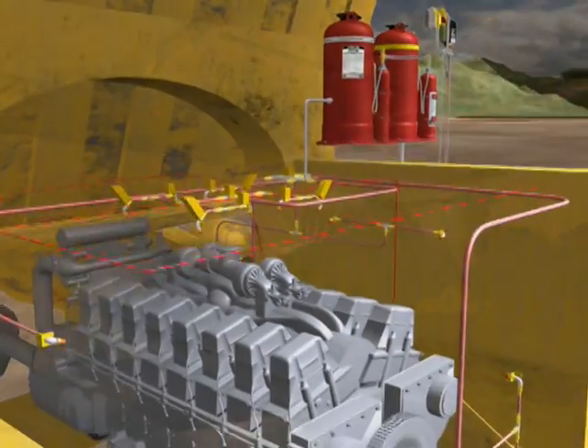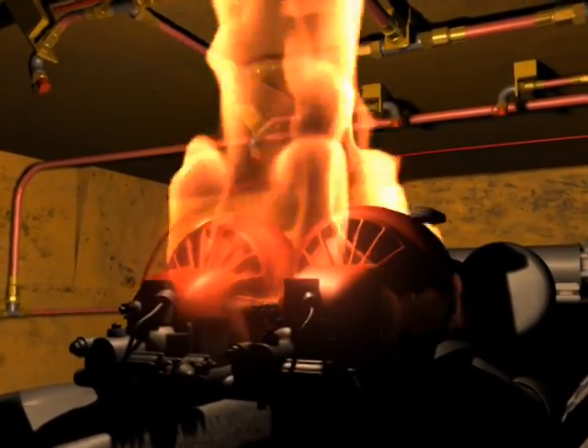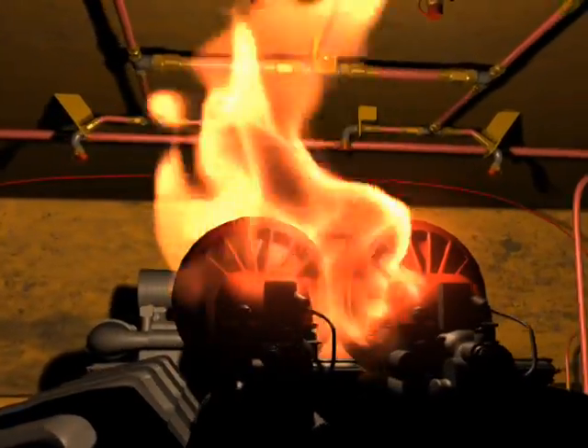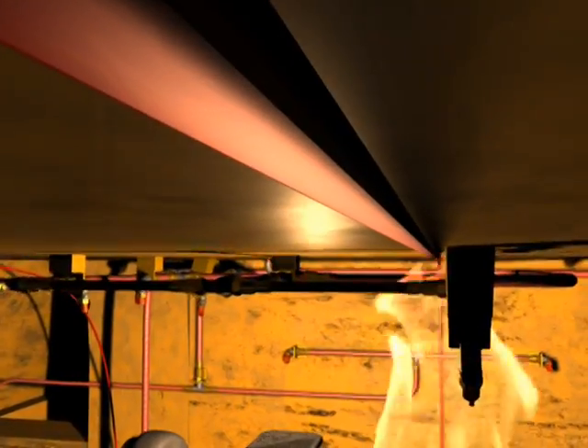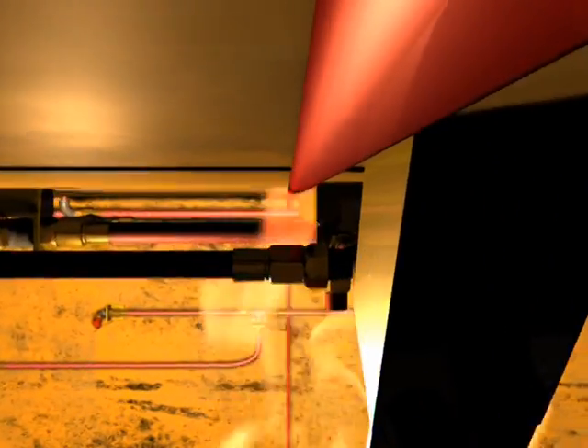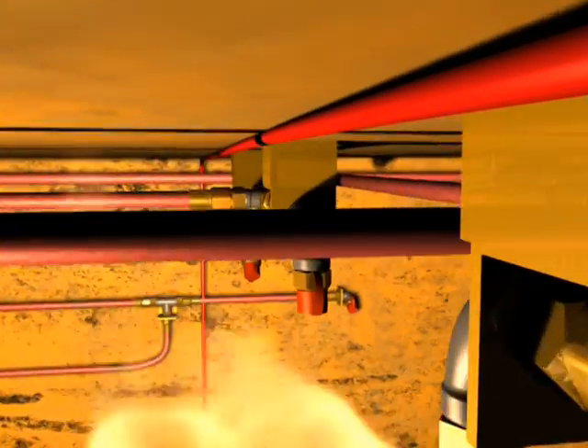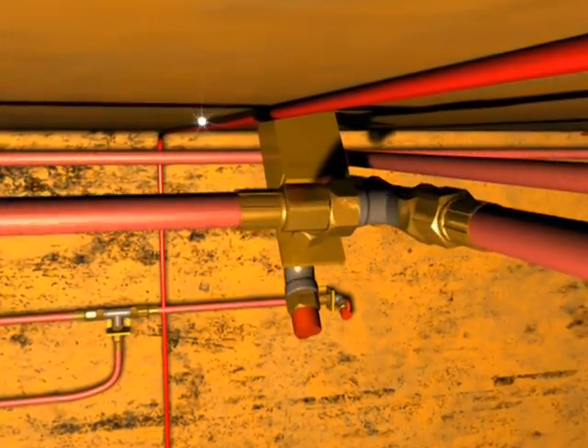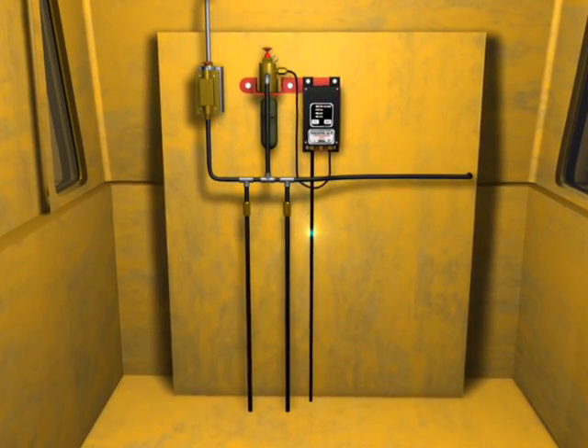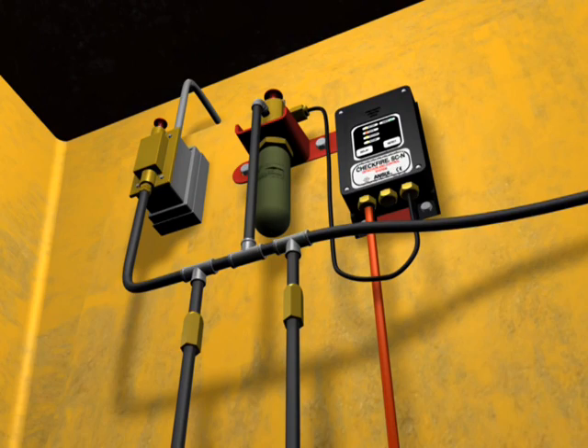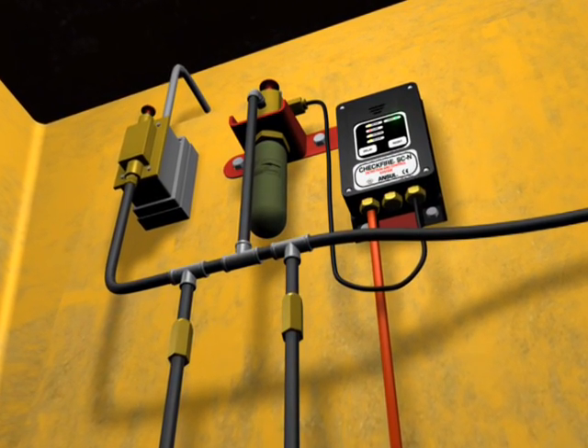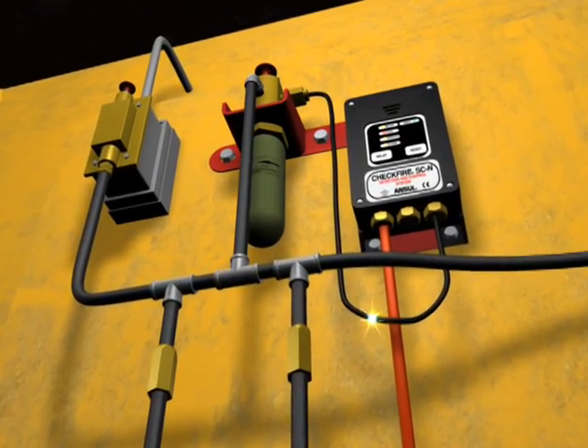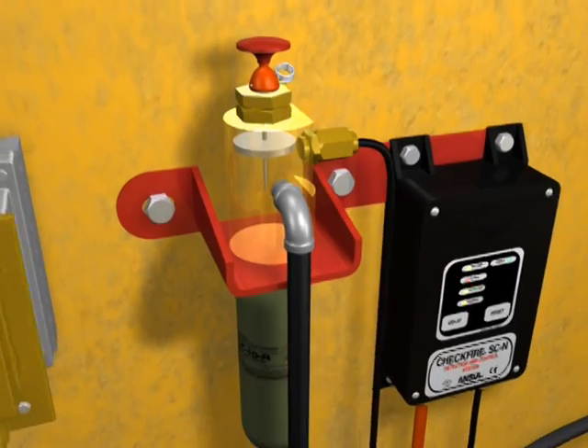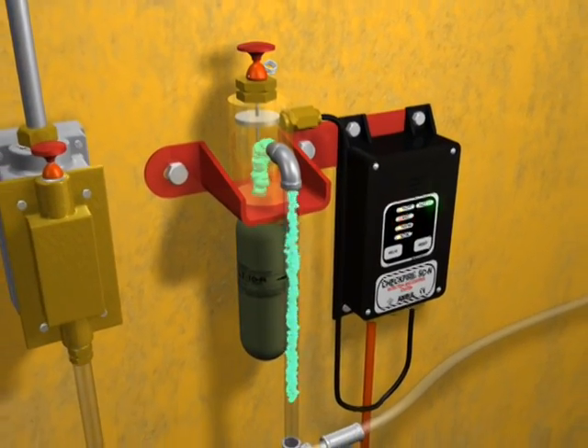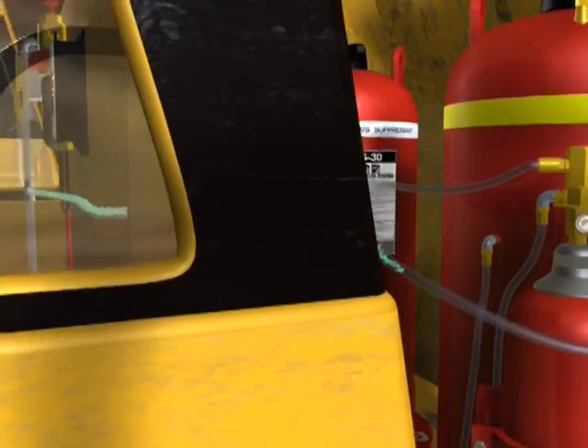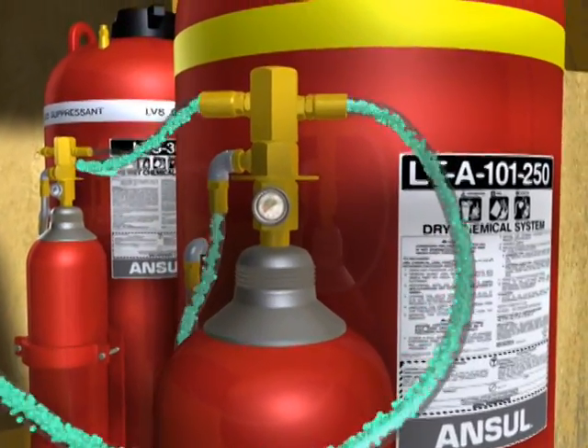When fire occurs, the Ansul LT-A-101 LVS twin agent system goes through a series of critical actions. First, the fire is detected by either thermal linear detection wire, thermal spot detectors, or the SharpEye triple IR detector. A signal is sent from where the fire is detected to the Checkfire detection and actuation module. The Checkfire SC-N module, after a predetermined time delay period, initiates system actuation by sending a signal to the fire suppression system. This signal initiates the squib in the actuation cartridge, sending pressurized gas to the expellent gas actuator. The pneumatic actuator punctures the seal on the expellent gas cartridge, which in turn pressurizes the agent tanks.